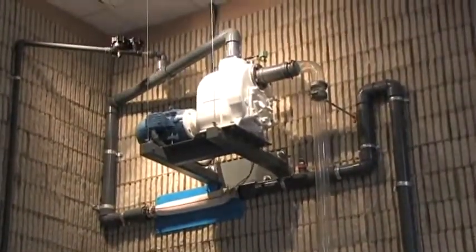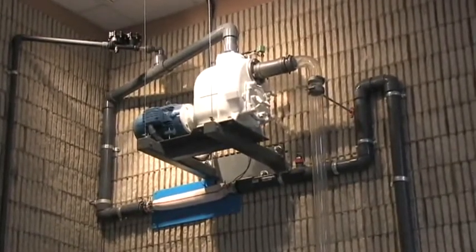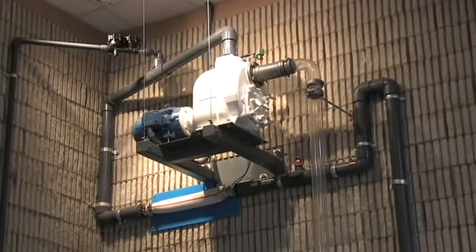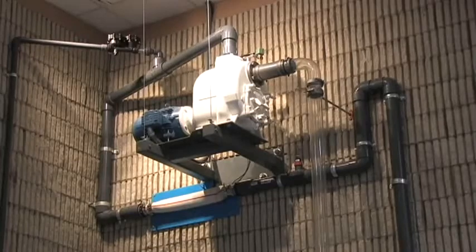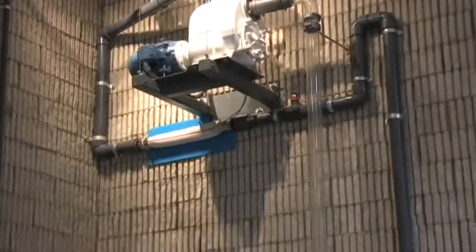All of our T-series and V-series pumps are designed so that they can reprime, or that they only need a minimum of a half a pump casing of liquid to get themselves primed. So there's no reason for someone to have to be out there filling these up with water when they lose prime in the field.